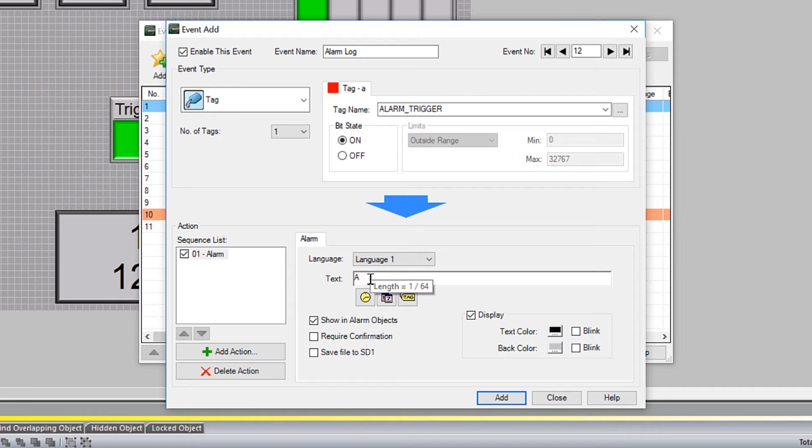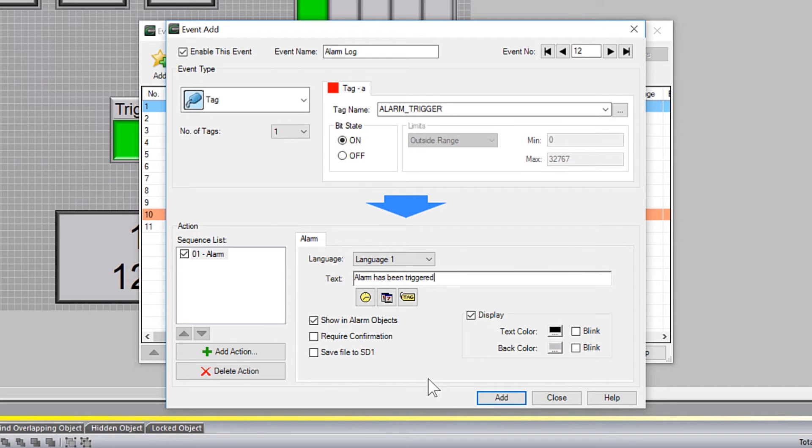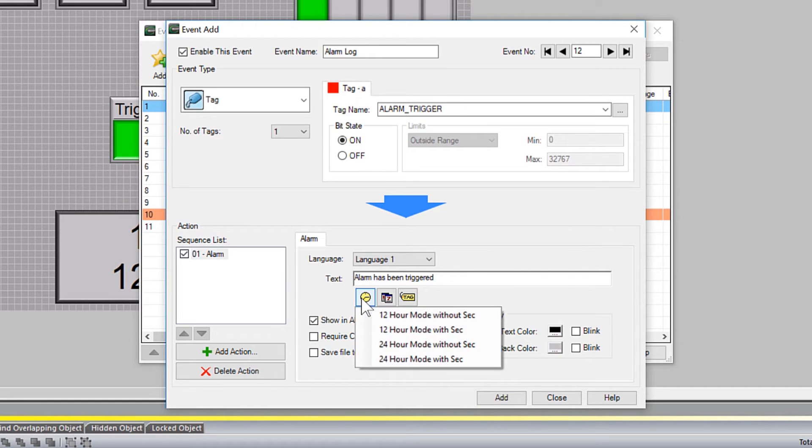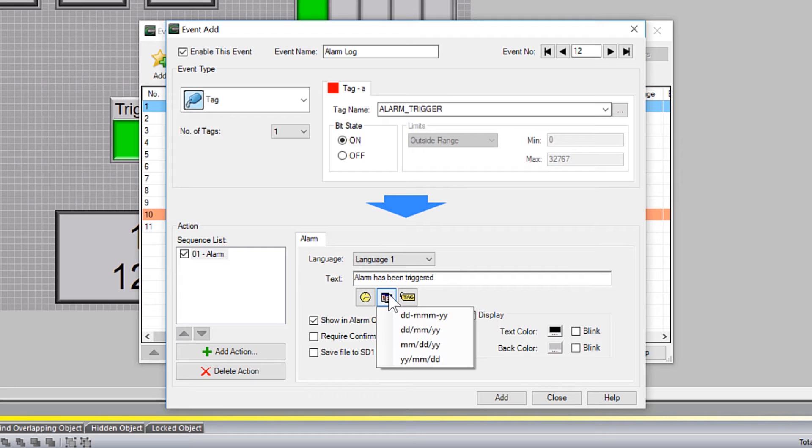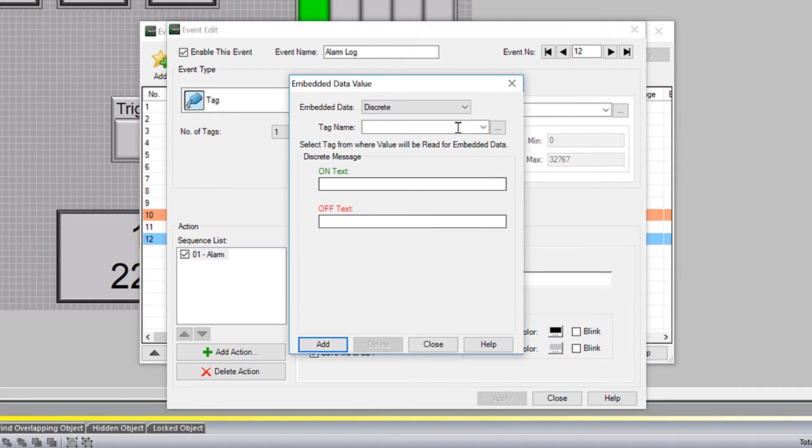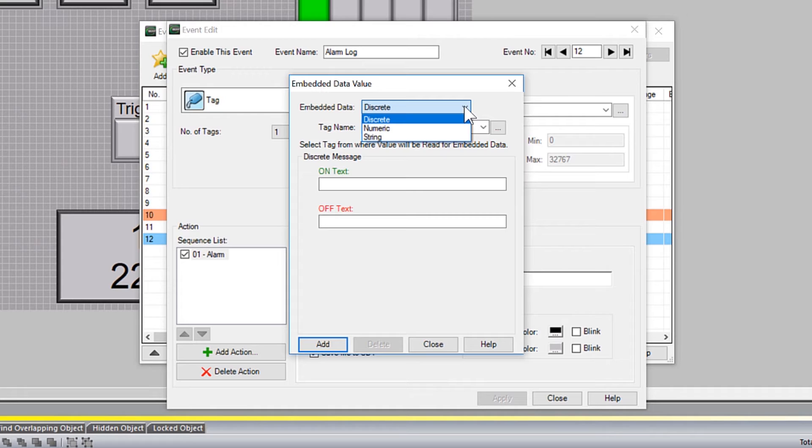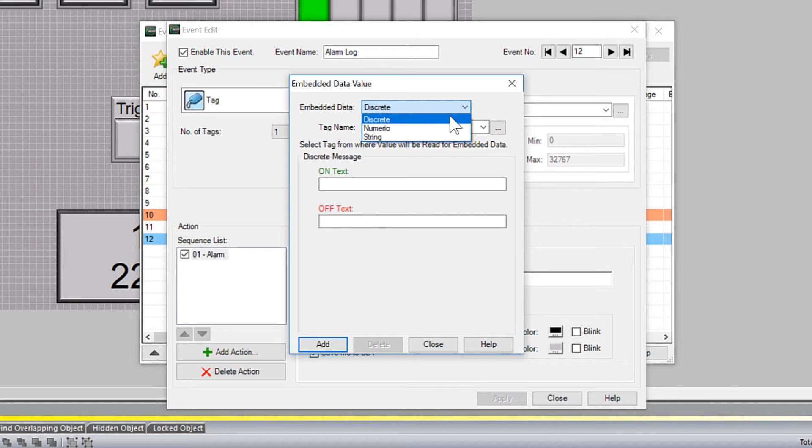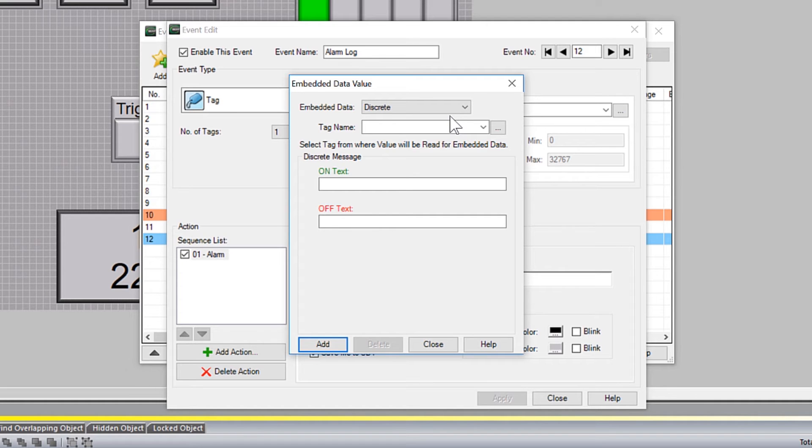This message will help in alerting the user and the technician to what the event is. The message itself can comprise of static text, have the time and date stamped into the message, or you can embed numeric, string or discrete tags. With the numeric and string tags, the value of the tag will be placed inside the message. With discrete, the on or off condition of the discrete can trigger different static text messages.